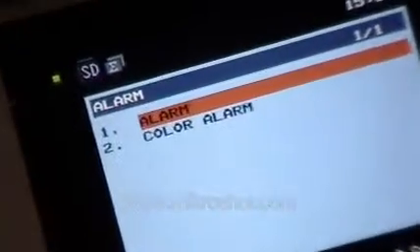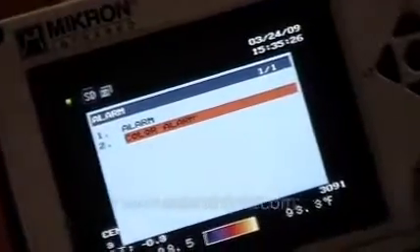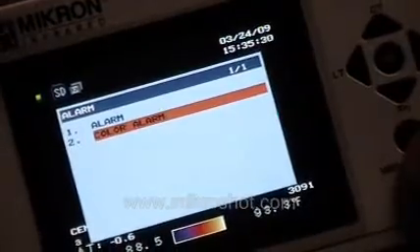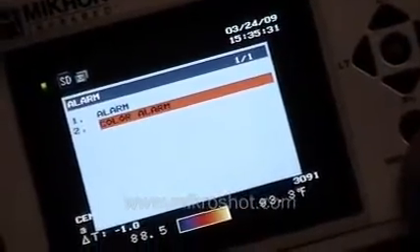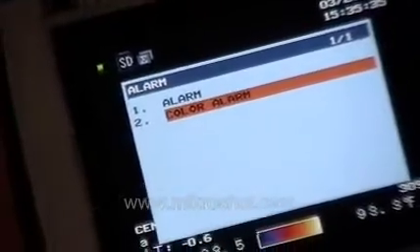The camera can also be set to alarm on exceedances above or below preset limits. We can also bring up what is called a color alarm or an isotherm, where we have preset temperature limits and colors that will indicate whether a target is above or below a certain temperature.